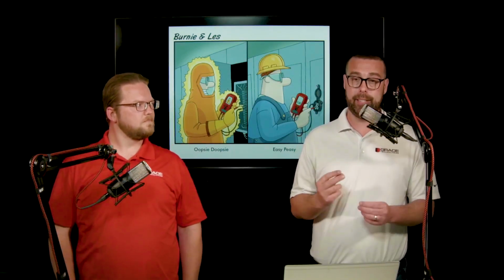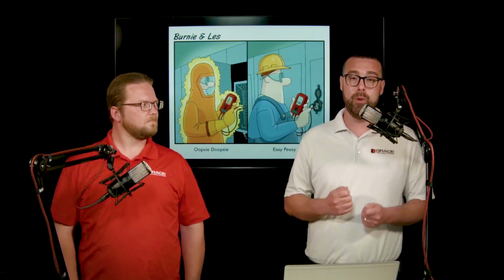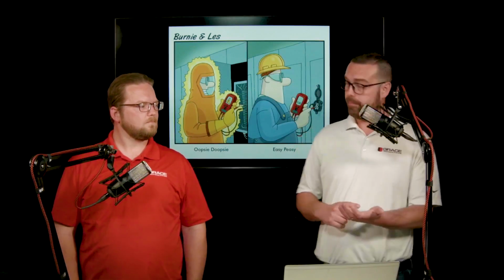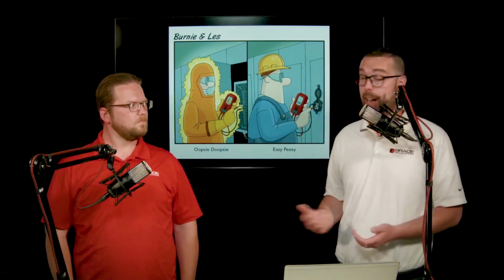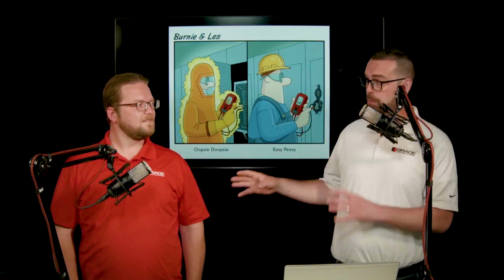The whole idea is that those are wired in parallel to your source voltage, giving you a safer alternative, keeping your enclosure door closed, keeping that harsh environment from getting inside your panel, reducing the time spent locking and tagging out your equipment, and providing you a return on investment in just 2 to 3 lockout tagout procedures, all while enhancing your compliance to electrical safety standards, specifically NFPA 70E. I don't know if we explicitly called that out.